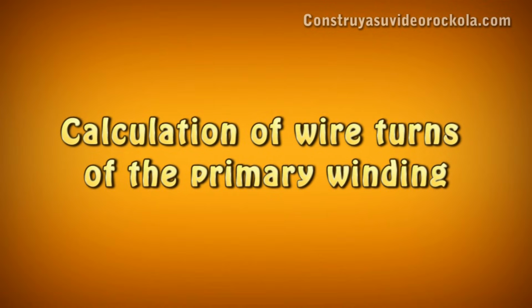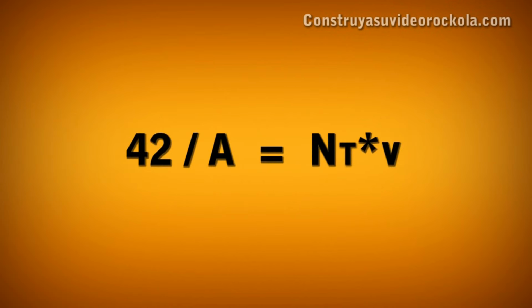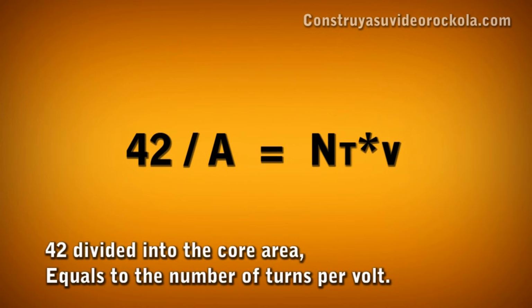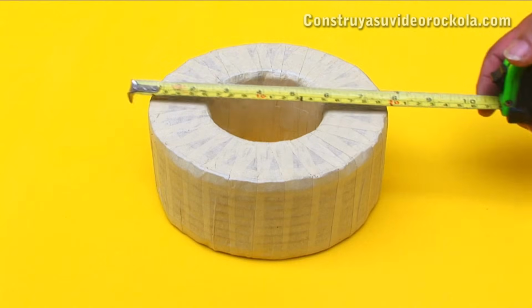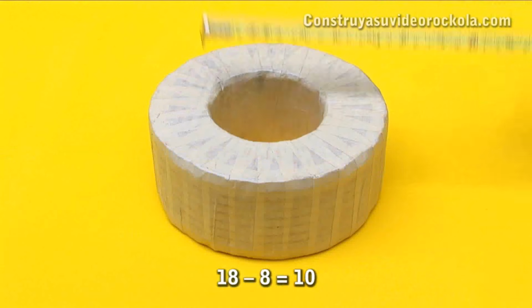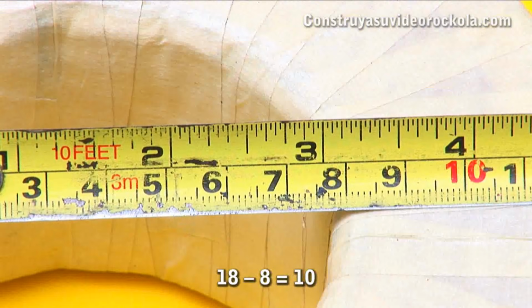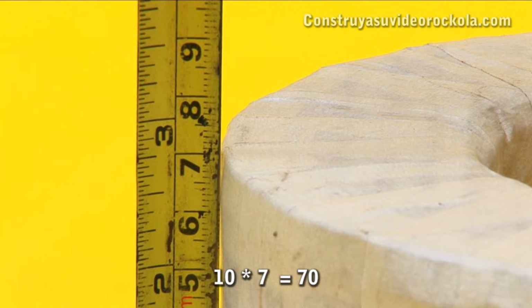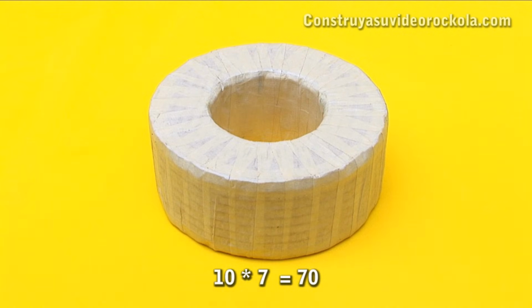Calculation of wire turns of the primary winding. As a general rule, we will use the constant 42. This is divided by the core area, resulting in the number of turns per volt for the core. 18 cm of external diameter minus 8 cm of internal diameter equals 10 cm. Then multiplied by 7 cm tall equals 70. 70 divided by 2 equals 35 square centimeters, equivalent to the core area.